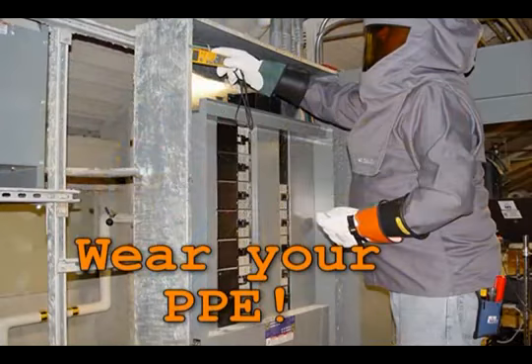This data will allow you to establish the flash protection boundary in inches, the flash hazard category, the minimum arc rating of your PPE and what PPE to wear, along with the limited, restricted, and prohibited approach boundaries. OSHA suggests that this information be present on the required arc flash warning label. The complete analysis will include your entire electrical system and nearly every electrical panel must be labeled.